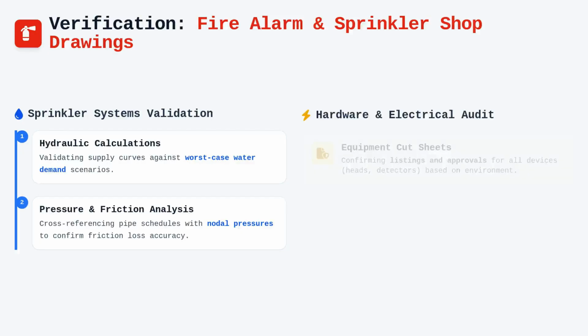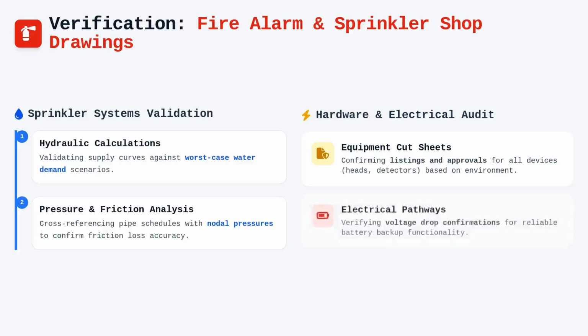Simultaneously, we inspect the equipment cut sheets to confirm that every device, from sprinkler heads to smoke detectors, holds the correct listing and approval for its specific environment. When we audit electrical pathways, such as notification appliance circuits, we look for voltage drop confirmations to guarantee that the system will function under battery backup during a power loss.